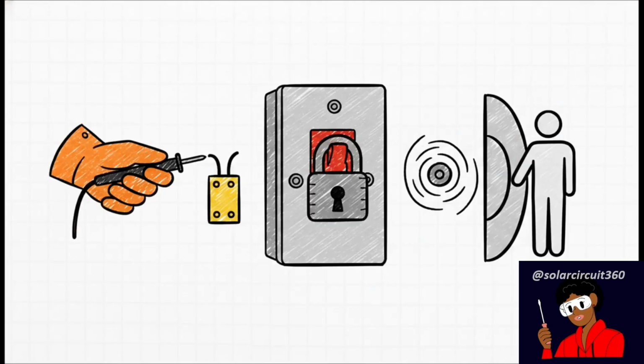So how do we actually prevent this whole mess without destroying our equipment or getting seriously hurt? Well, before we even touch a testing instrument, safety is absolute. We have to talk about it. Three-phase commercial systems contain potentially lethal voltages and significant arc flash fault energy. You absolutely must follow strict lockout/tagout procedures. Never ever attempt to swap conductors on energized equipment just to see if it fixes the rotation. Just don't do it. Always verify that voltage is entirely absent before modifying any connections.